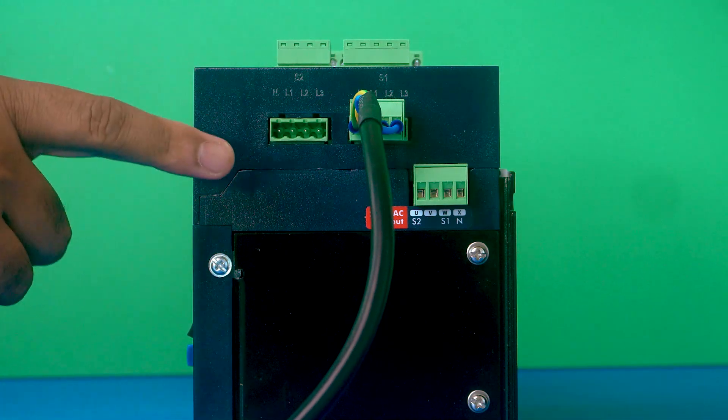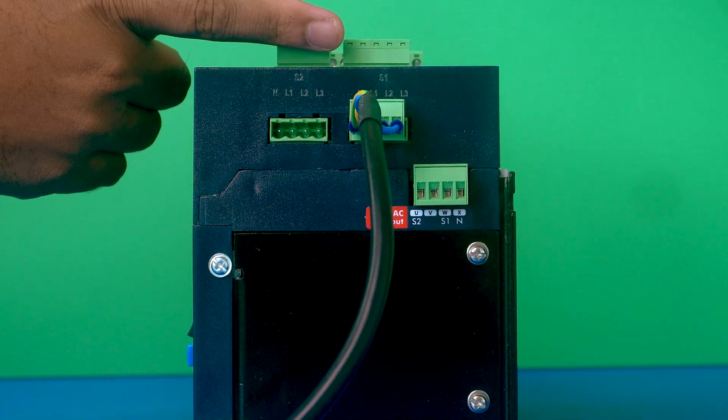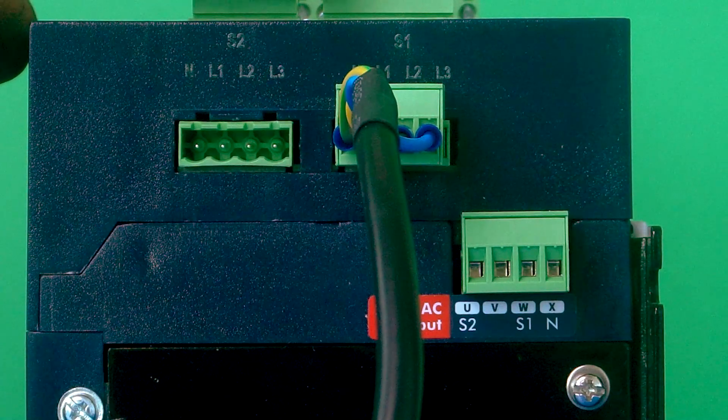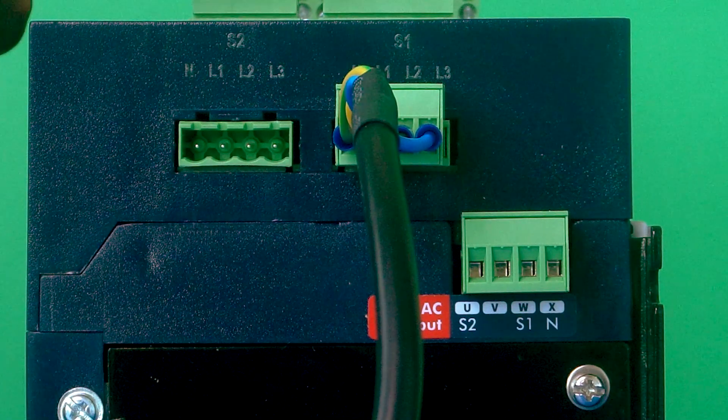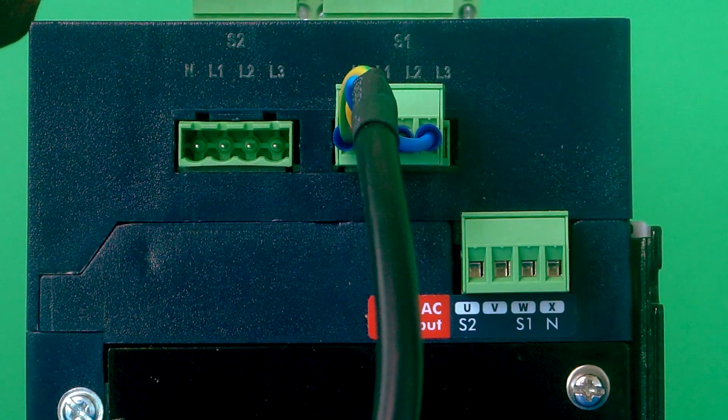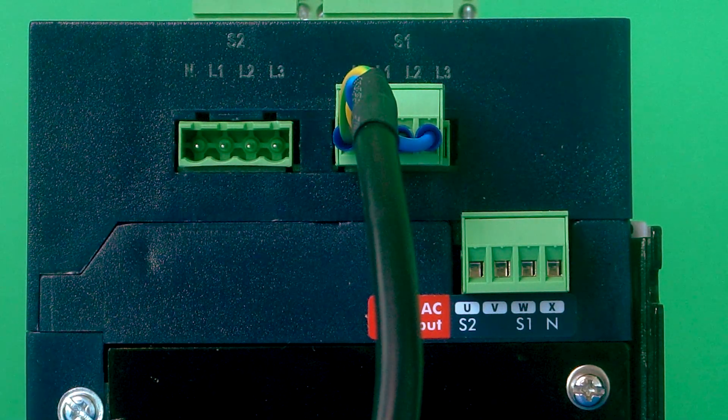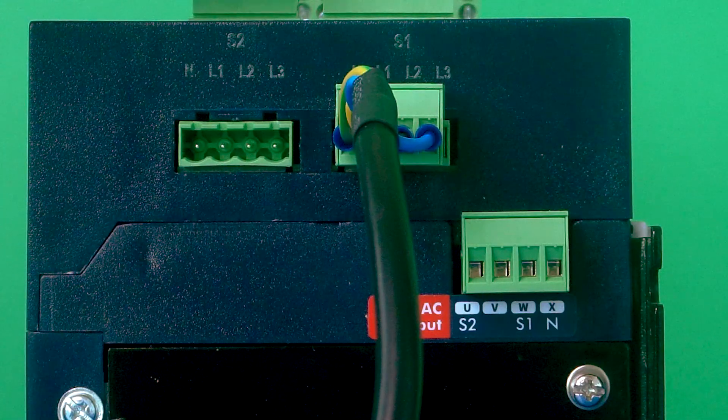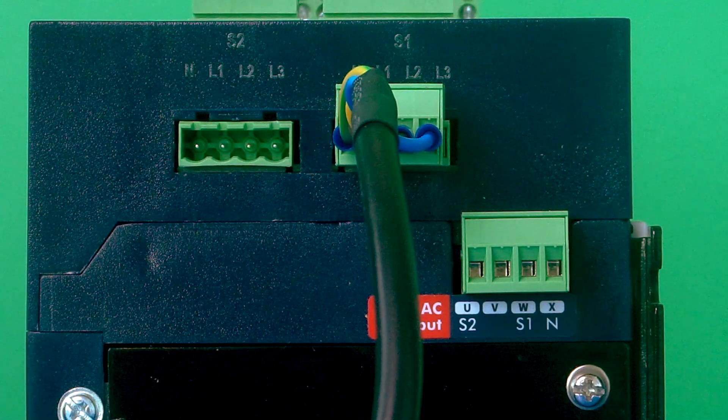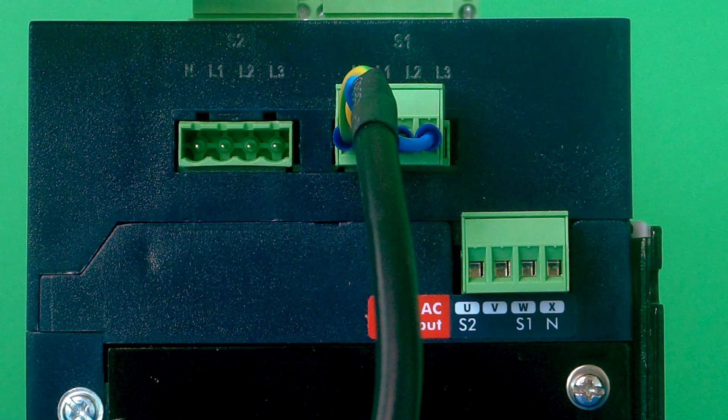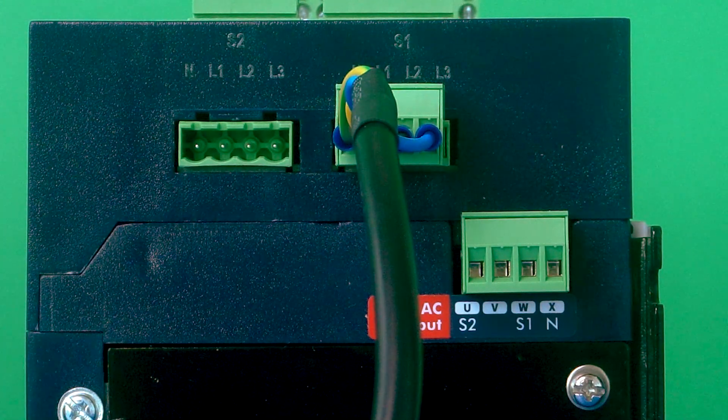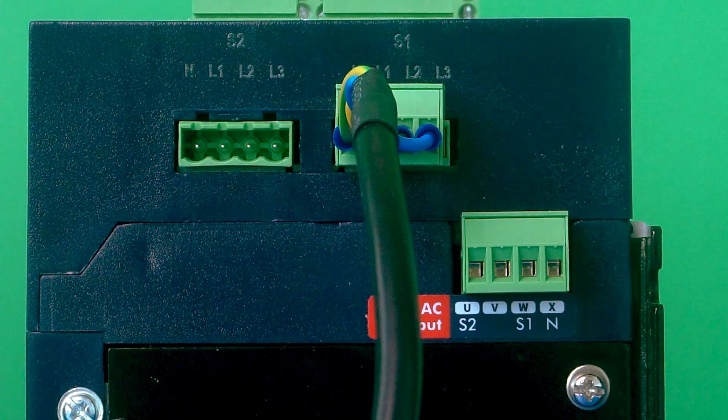Now it is connected. There is terminal identification like neutral, L1, L2, L3. We should not change any wiring here - we can change the wiring on the incoming spreader side, not on the connector side.